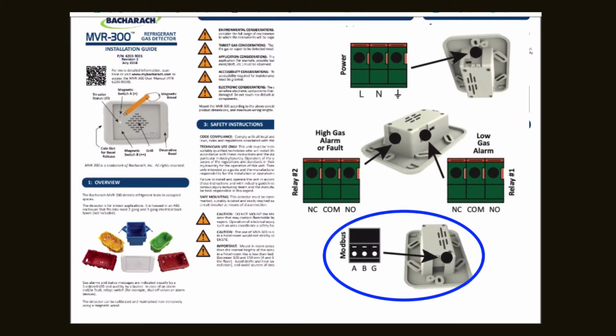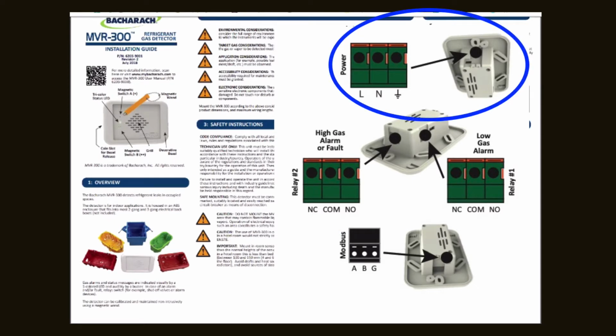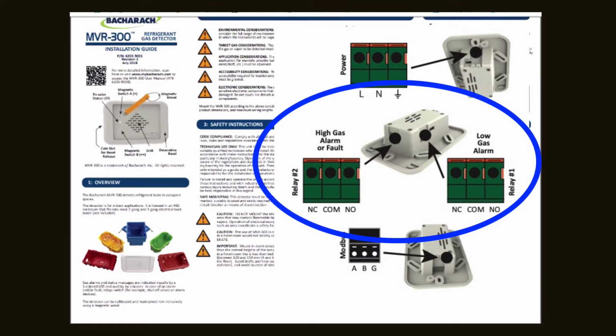The thing that I wanted to cover first was the MVR-300, and this is the actual gas detector. This is the gas detector that's going to be in the rooms, in the occupied spaces. It will detect the gas. It's got a Modbus interface. It's got a power input, 120 volts input. And then it's got 2 alarm relays that can also be used.